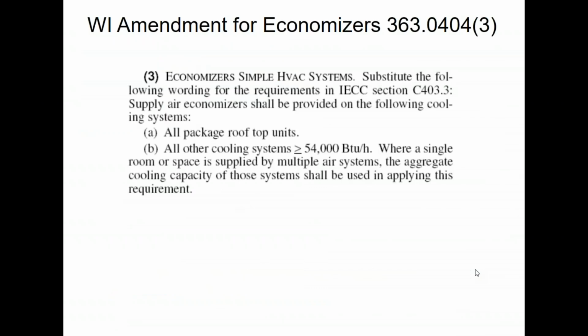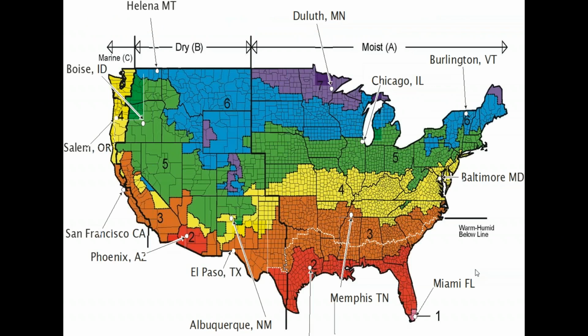You still have to do the economizer when it's 54,000 BTUs and up. And additionally, all rooftop units have to have an economizer with no size limitation. So a 4-ton, 3-ton, 2-ton rooftop unit would have to have an economizer. Split systems, 54,000 BTUs and up in Wisconsin.